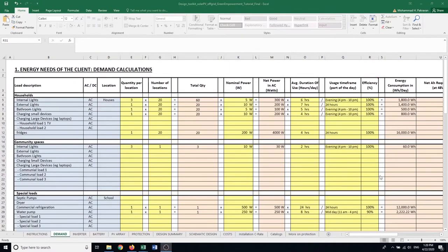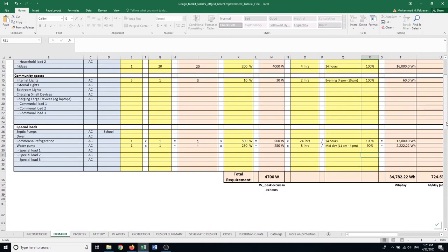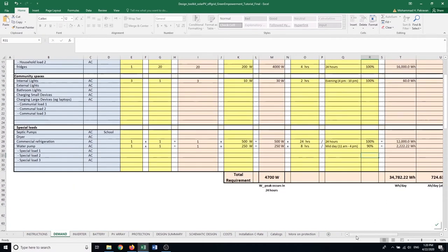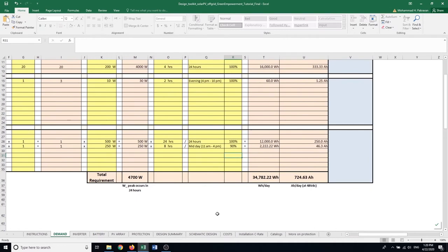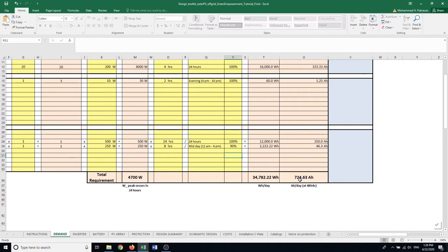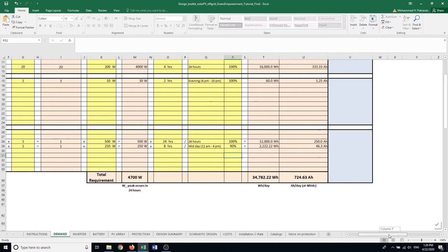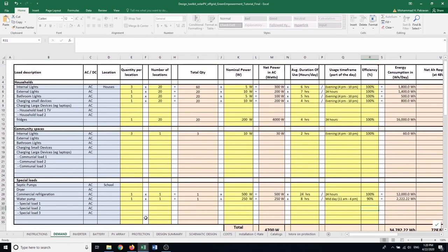So now that I have imported all the loads in my hypothetical example, there are a couple of items that I can see at the bottom of the table. First one is the maximum, the peak power that I'm going to need every day, and then the total energy required each day, and then the total amp hour, the capacity of the storage that I'm going to need every day. With the information here, now I'm ready to move on to the next tab for designing the inverter.